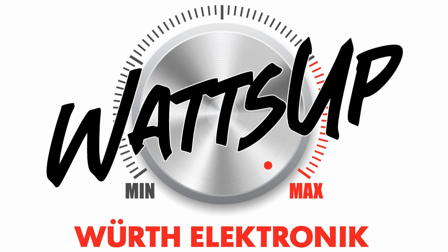For example, you can see here that even if the normally rated voltage is 2.7 volt at 65 degrees, we can go up to 85 degrees if we reduce the voltage rating to 2.3 volt. In this case, we consider end of lifetime to be when the capacitance has dropped to 30% of the original value. We have developed a model to calculate supercapacitor lifetime with different loads. If you want more information, please contact us.